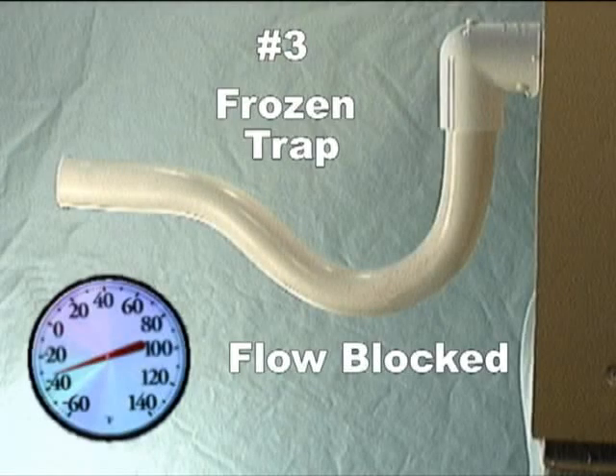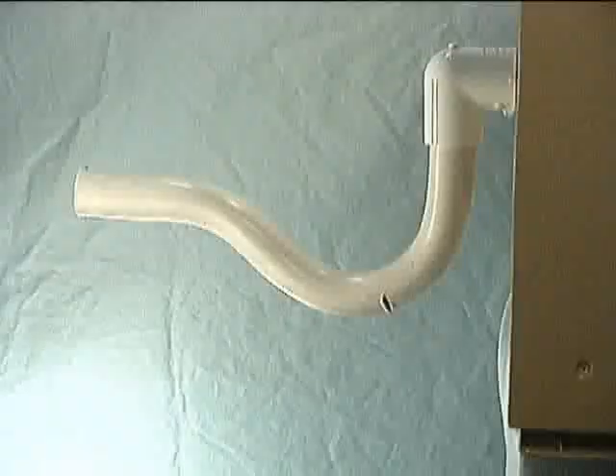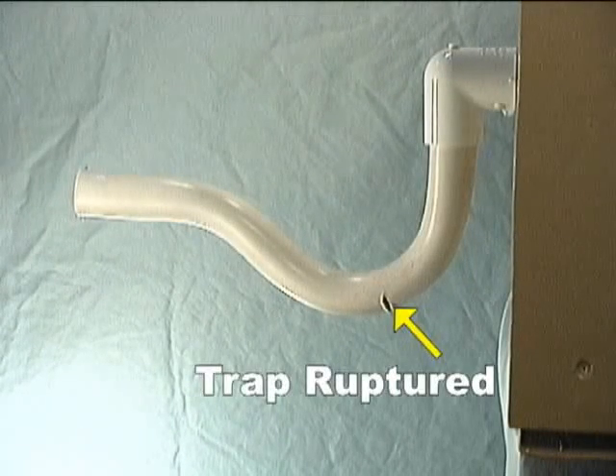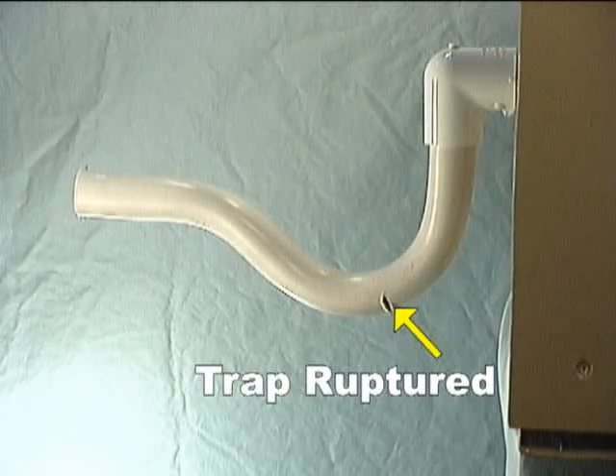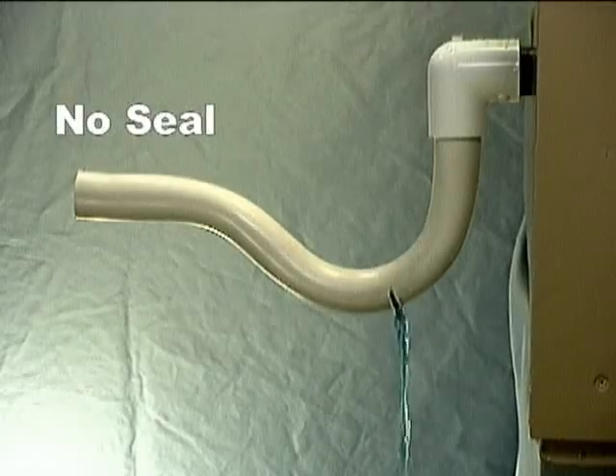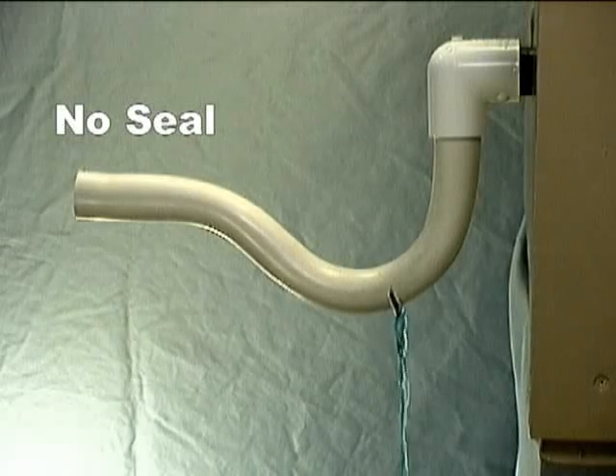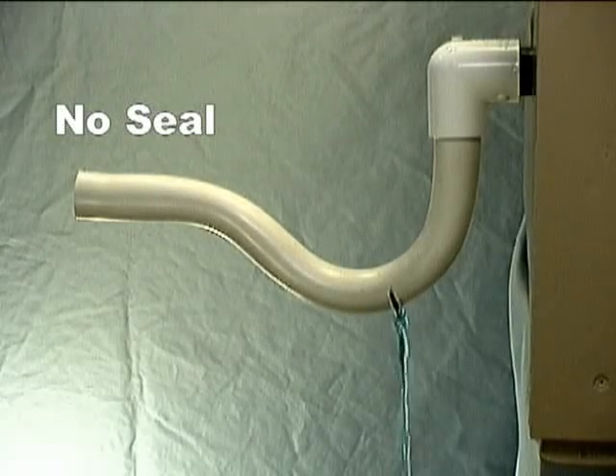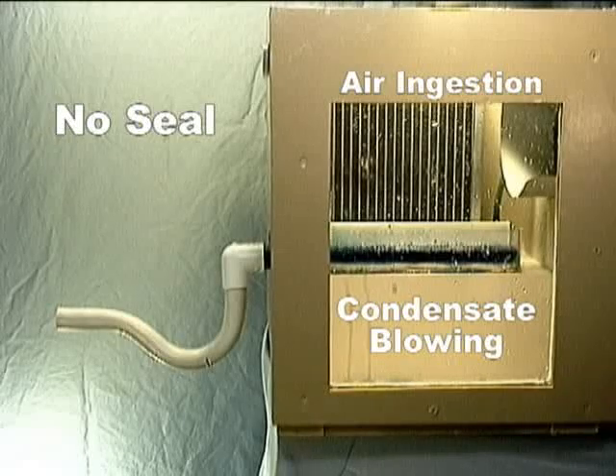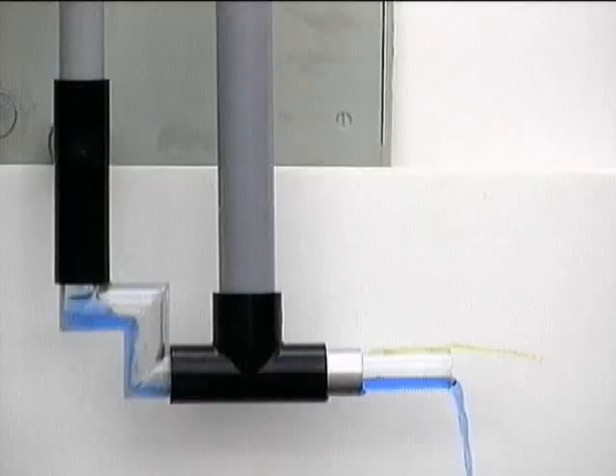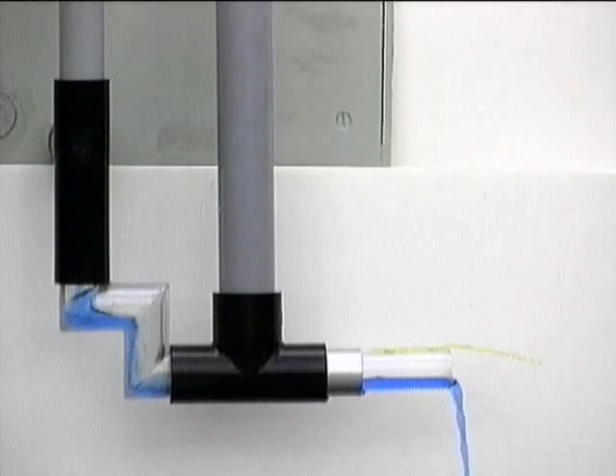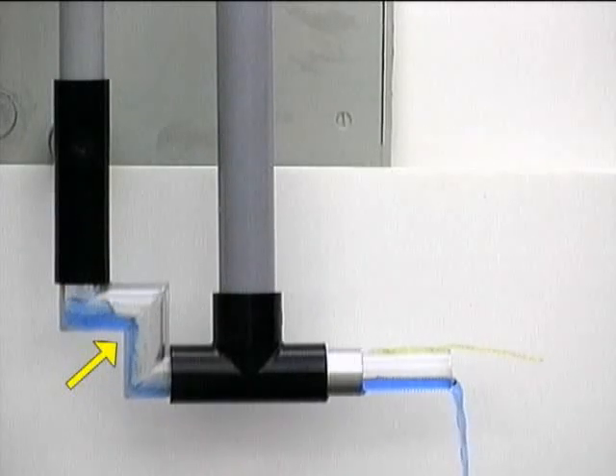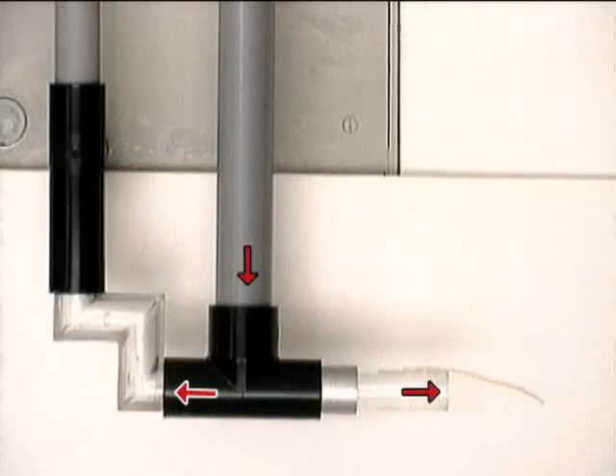Condensate traps exposed to freezing temperatures will block the flow of condensate, causing drain pan overflow. When condensate freezes, the trap is frequently ruptured, as depicted here. Because it cannot retain condensate, there is no seal and it acts like an empty or missing trap. Observe that water leaks from the trap and allows air ingestion and condensate blowing during the cooling operation. The CostGard Condensate Drain Seal retains no condensate. Once condensate flow ceases, the warmer air that forms the drain seal quickly evaporates any water that may be held in place by surface tension.